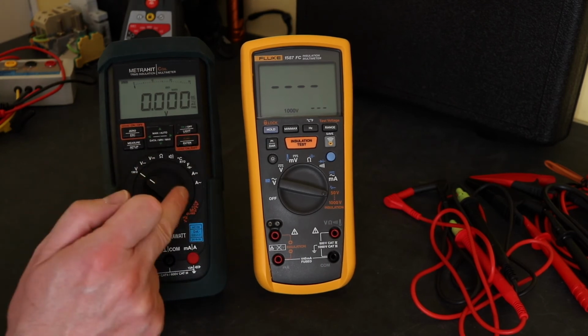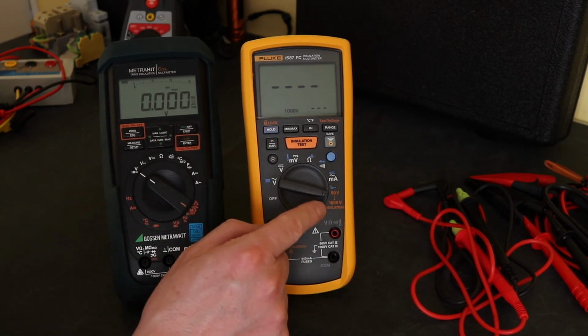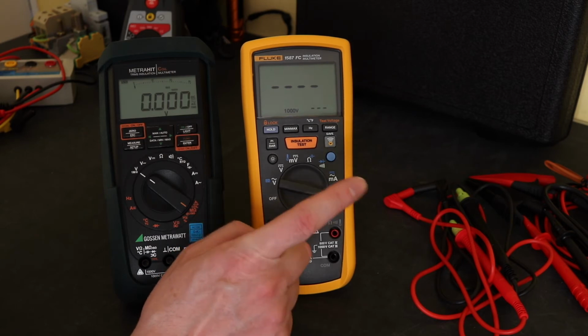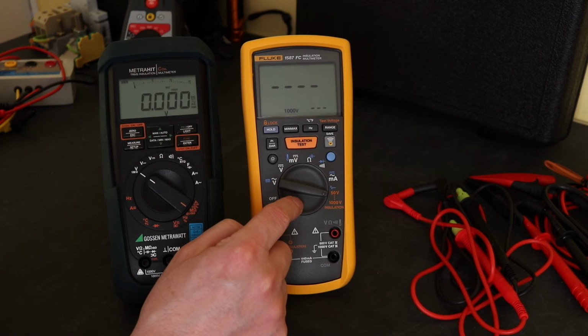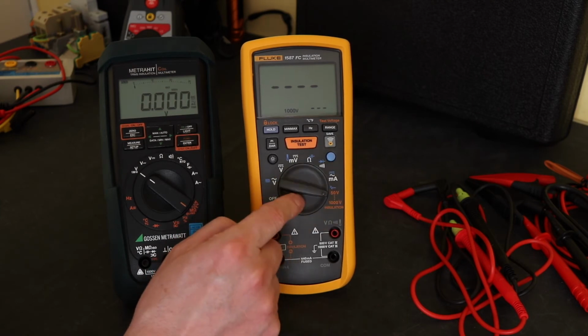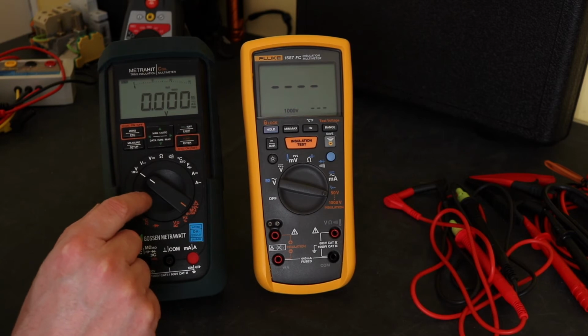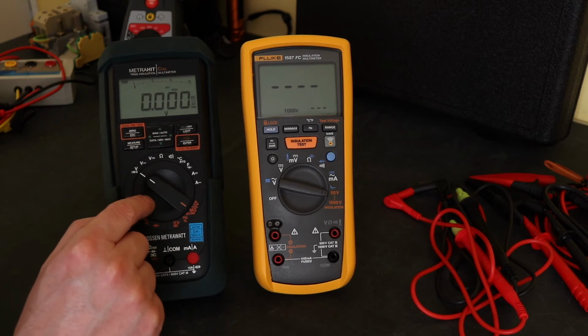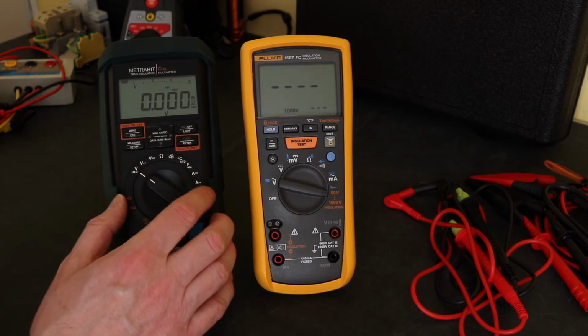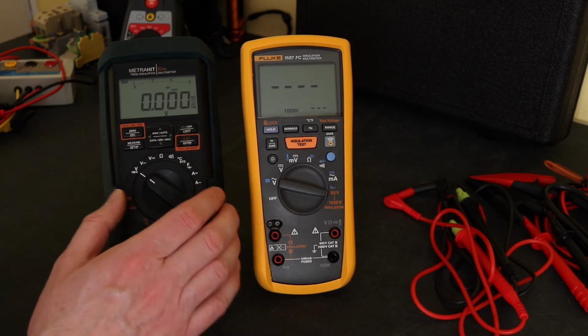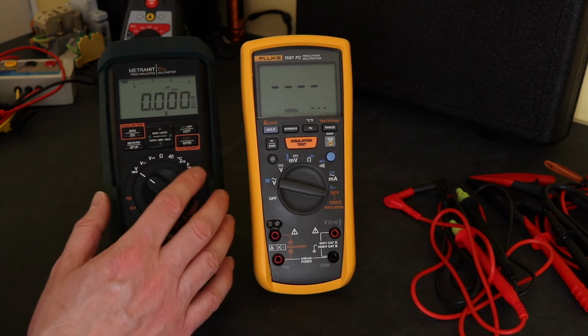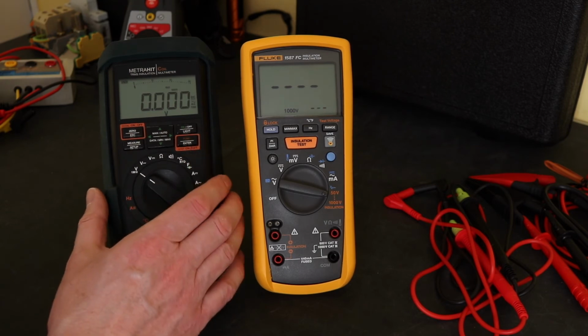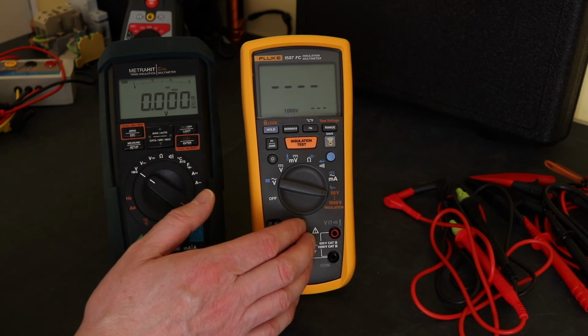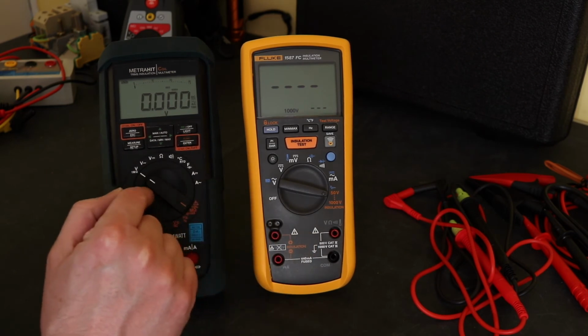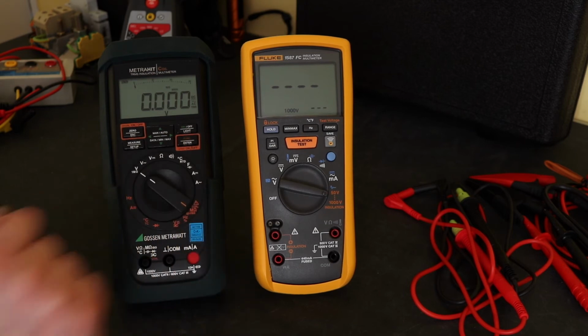So for insulation testing range, this will go up to 2.2 gigaohms at 1000 volts, but then drops off to 550 megaohms on the 500 volt setting and keeps going lower. This is 310 megaohms at 50 volts. All the other ranges, 100 through to 1000 volts, are 3.1 gigaohms. So it does have a higher test insulation value capability than the Fluke, but to my mind, with the rest of the stuff that's going on, with the way it operates, I'd sooner have test capabilities of this rather than the higher test range. But that's just my opinion, of course.